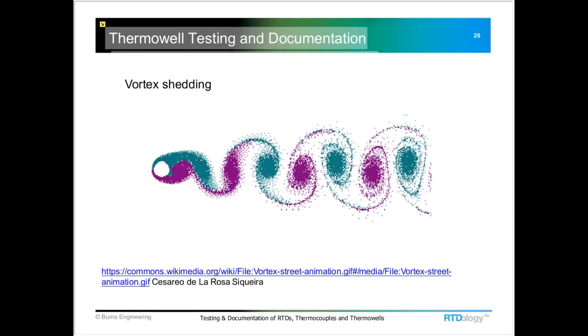So first, when we have a Thermowell stuck in a flow, we get these little vortices that form downstream, and if the frequency of these vortices matches the resonant frequency of the Thermowell, it is going to start to vibrate, the temperature probe is going to fail, and then eventually the Thermowell will fail. Either it will break or it will crack and start leaking. And so we really need to be aware of that phenomenon.